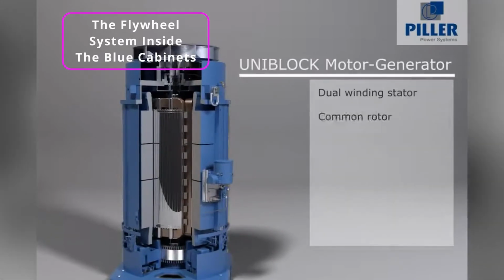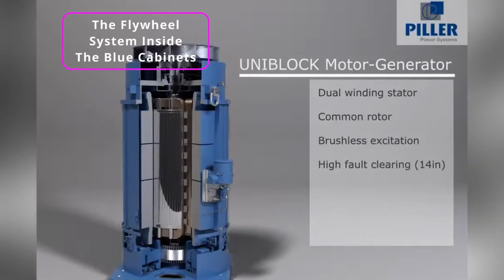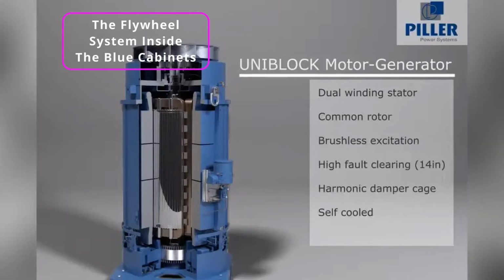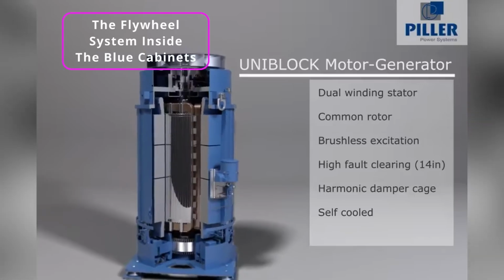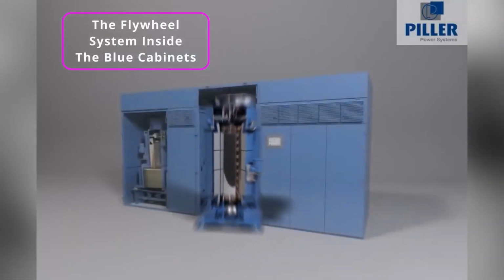How much maintenance is there? They're pretty maintenance-free, I'm assuming. They're pretty maintenance-free, but there is still a fairly rigorous schedule to it. Yeah. The floor here had to be laser leveled to make sure everything was nice and flat. And then these things have to be calibrated and maintained, and if there's an issue, your on-site team needs to be certified to do the maintenance. Again, hermetically sealed is a little bit of a challenge to do on-site, but that's why you have redundant numbers of these in a data center.